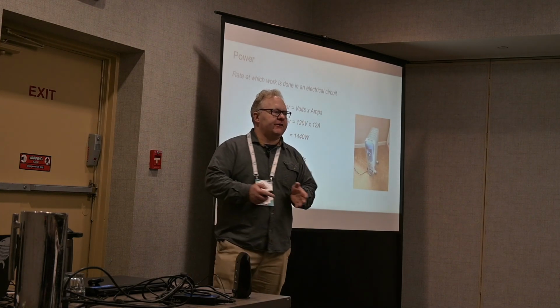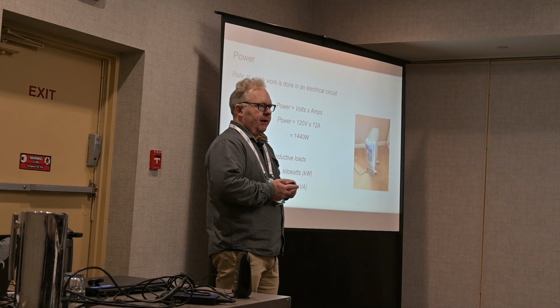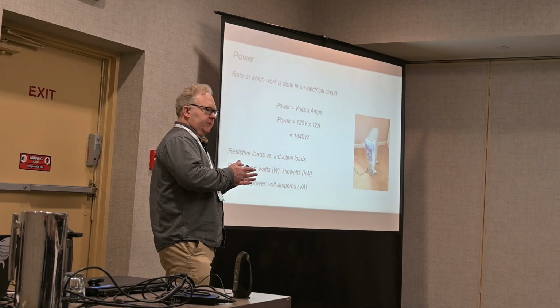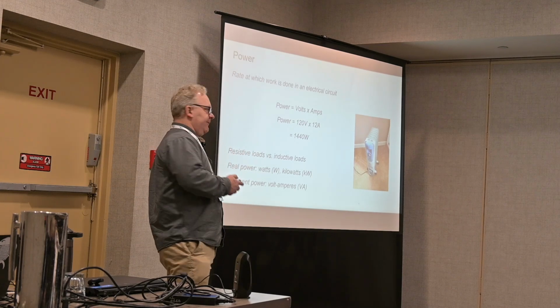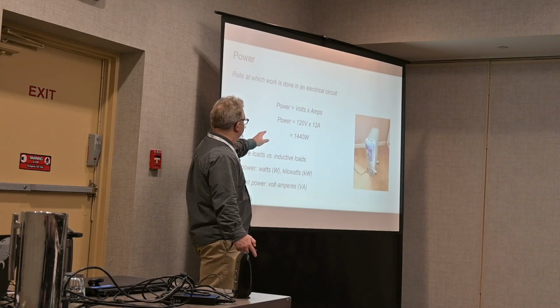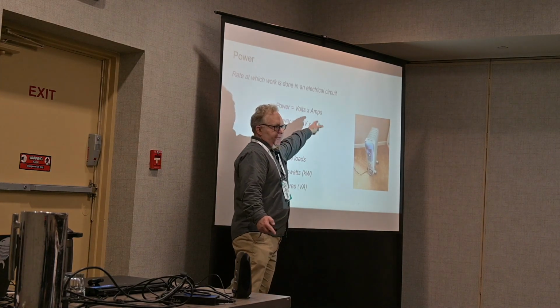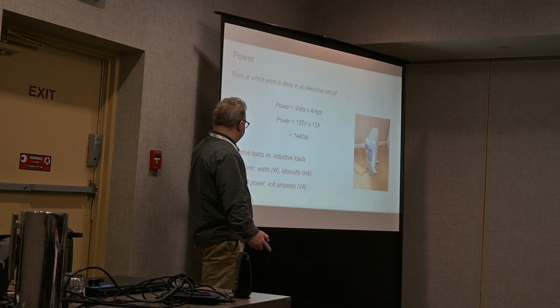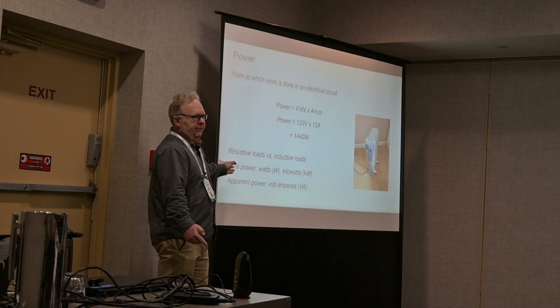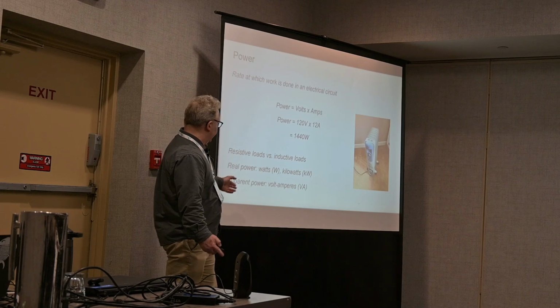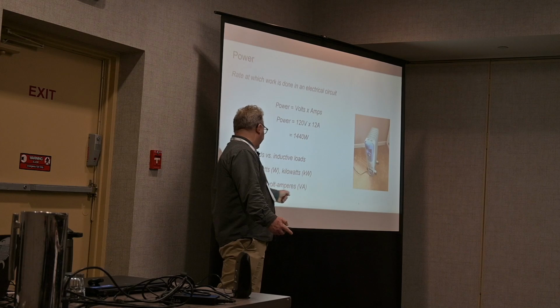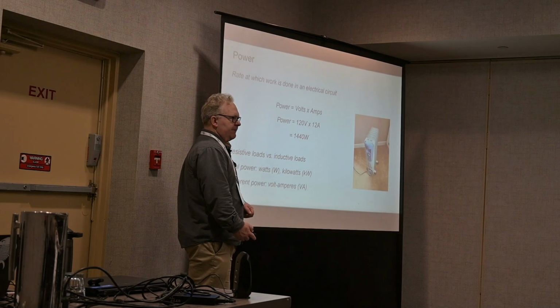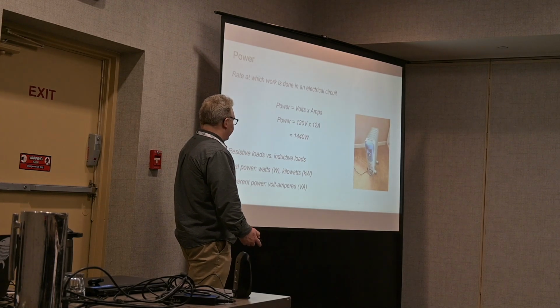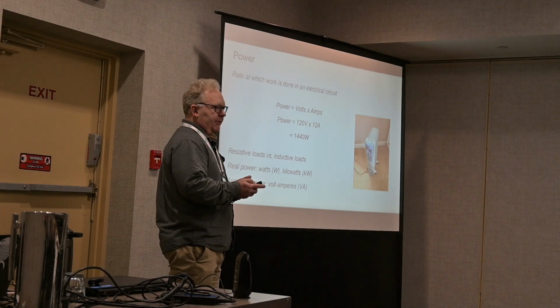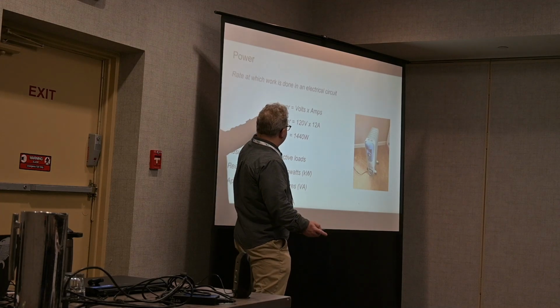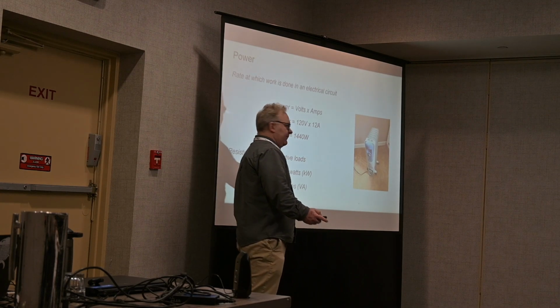When we've got an inductive load, essentially an induction motor, these are designed so that the current flow and the voltage are slightly out of phase. And in those, the power will be slightly less than the volts times the amps. And that's called apparent power. In practice, these are so similar that for the calculations that we're going to be doing, we're going to treat them the same. So we can use either watts or volt amperes in our panel sizing calculation. If you want to drill into that further, it's pretty interesting stuff, and it'll help you understand better how electric motors work. But for our purposes today, we can add up our loads either in watts or in volt amperes.